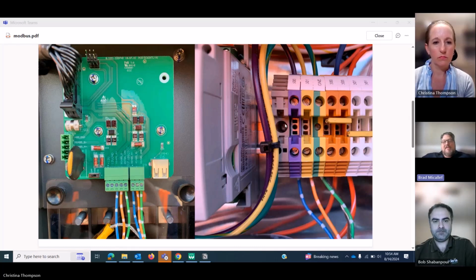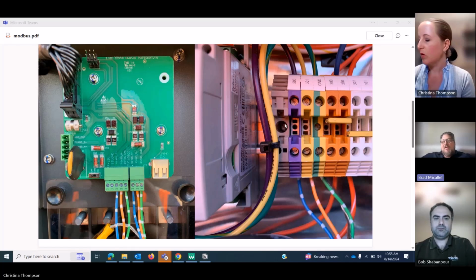Each inverter has its own device ID, but you also have registers being pulled for all those devices. At the end of the chain, those serial wires, that blue, orange, and green, finally end up in some type of control cabinet. In this case, they're landed on some terminal blocks, and they ultimately go to a data logger that is already communicating with those inverters.